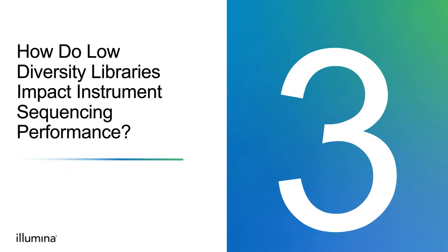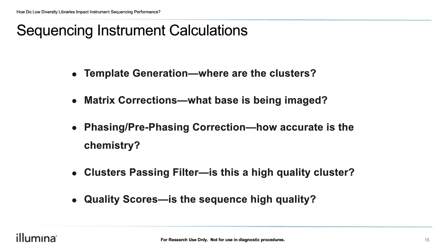Now that we have an idea of what nucleotide diversity is and how we can review it using sequencing run metrics, let's take a closer look at how nucleotide diversity actually impacts sequencing run performance on Illumina instruments. During the sequencing run, the instrument will collect data from each of the clusters and use this data to perform a variety of calculations, including template generation, matrix correction, phasing and pre-phasing correction, clusters passing filter, and the quality score.